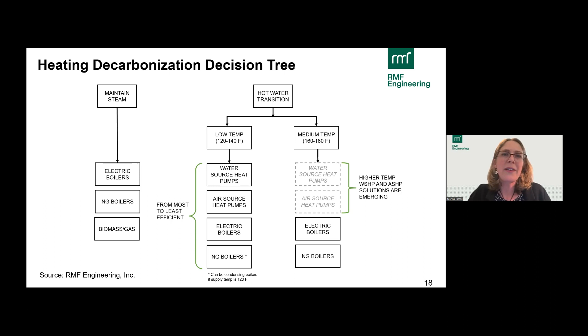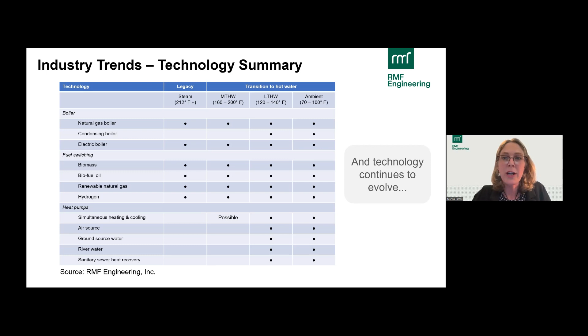But again, here's another way of displaying this. When you move to these lower temperature hot waters, what we'd call low temperature hot water, maybe between 120 and 140 degrees, or ambient loops which are even lower, there are many more highly efficient equipment options available. That's not to say these aren't developing for higher temperatures, but this is why you might be seeing presentations at IDEA about these massive transitions from steam to hot water, and not just any hot water, but low temperature hot water. Why do we do that?